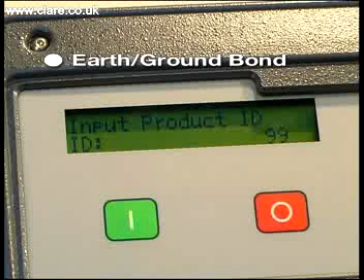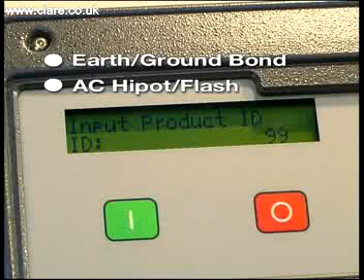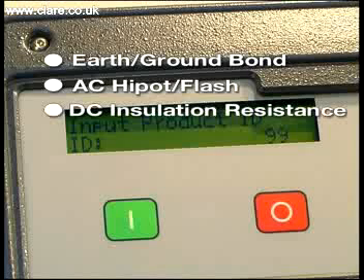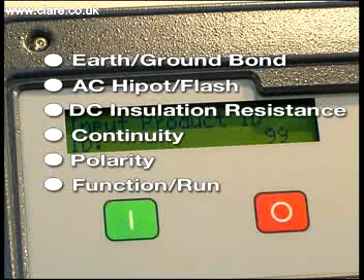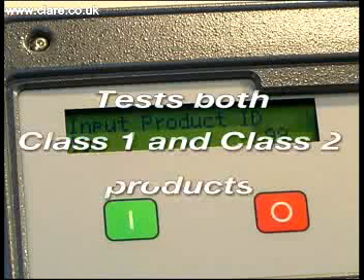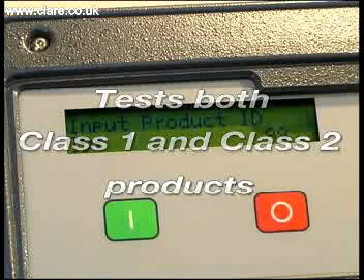This comprehensive unit allows the user to carry out the following tests: Earth Ground Bond, AC Hipot Flash, DC Insulation Resistance, Continuity, Polarity, and Function Run Test. This enables the user to test both Class 1 and Class 2 products simply and efficiently, meeting the required test standards.